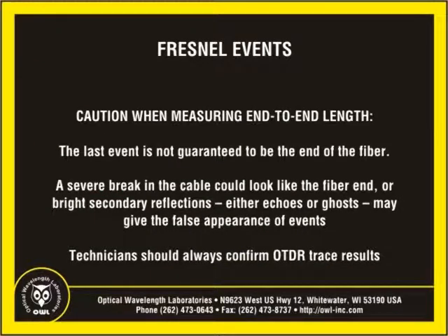It should be noted that the last reflective event is not guaranteed to be the actual end of the fiber for a couple of different reasons. Severe events such as breaks mid-span might prevent the OTDR from detecting other events beyond the break. Also, echoes or ghosts from previous highly reflective events might appear in the noise area of the OTDR trace beyond the actual end of the fiber. In either case, it is up to the technician to confirm the results shown on the OTDR trace.